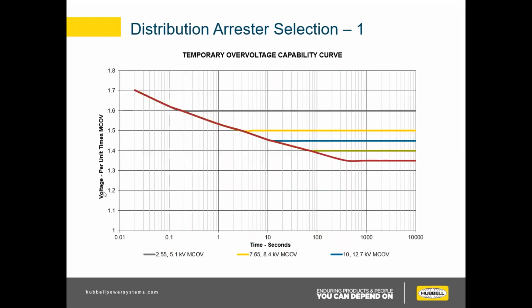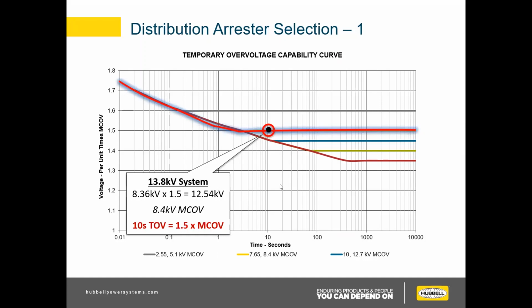Let's see. Here we go. Okay, so this is our TOV capability curve. This is another thing that we really spend a lot of time working on and honestly looking at. So that same 13.8 system or 13.2 system, 13.8 maximum, so that's with your voltage regulation. If you have a 1.5 per unit TOV for 10 seconds, we can find that on this chart here, and anything to the left or below the line here means you're in the clear.